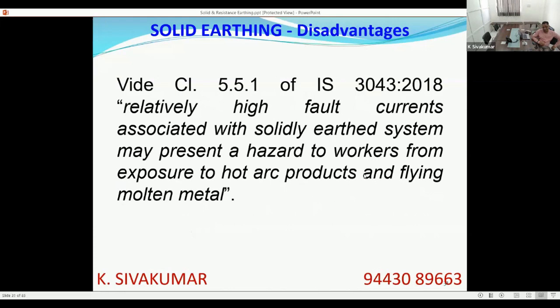And in IS 3043 also, in one place it is documented: relatively high fault current associated with a solidly earthed system may present a hazard to workers from exposure to hot arc products and flying molten metal. So it also acknowledges that high fault current is a disadvantage. Of course, there is a second part to this. It is said that most of the industrial systems are metal enclosed switchgear. So this may not be taken very seriously, because metal clad and metal enclosed switchgear are generally tested for internal arc. So they say, but definitely the disadvantage is recorded in IS 3043 also.